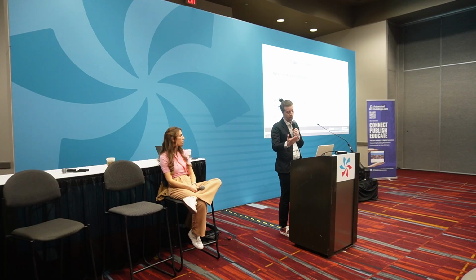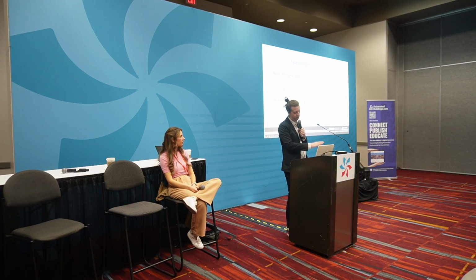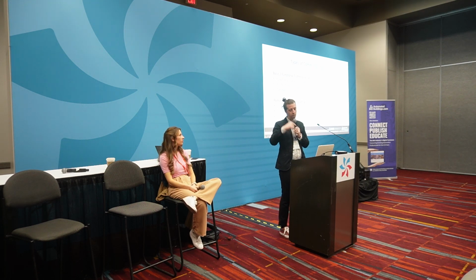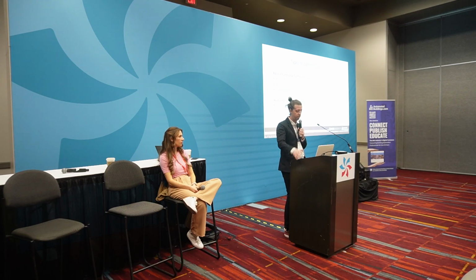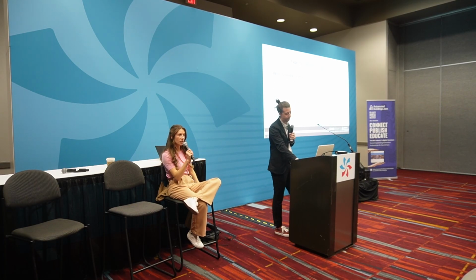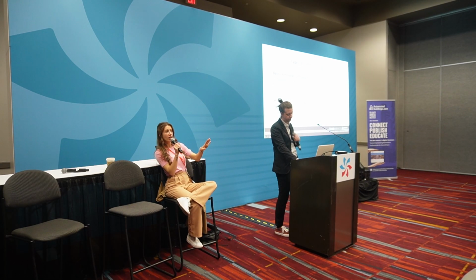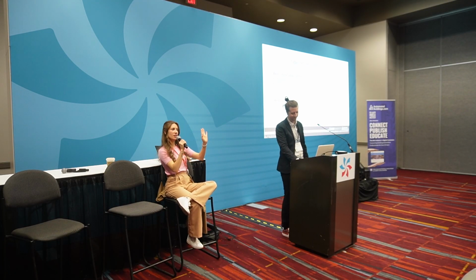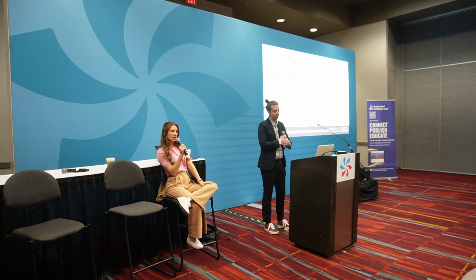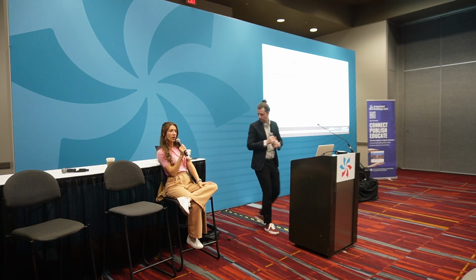And that's where I want the contractors, especially the good ones, to come to us and say, listen, we've got better ways of doing this. And we take their advice and update things. If we have that conversation before they start programming, we're not having to go back and fix all those things during commissioning, because guaranteed those will end up being problems we find, and then we have to say, okay, we've got to change it. And at that point we're already past into the warranty period, and it's way better to solve those problems up front. For the contractors in that room, that advanced performance commissioning where we saved all that, contractors all got change orders. Everybody was happy, client was happy, and that net cost way outweighed the second phase.